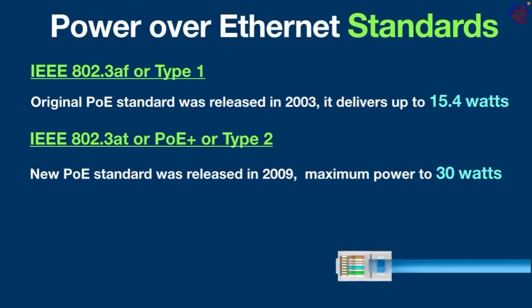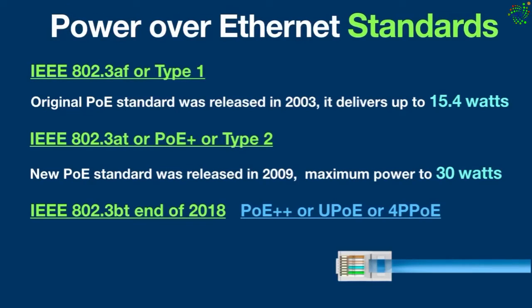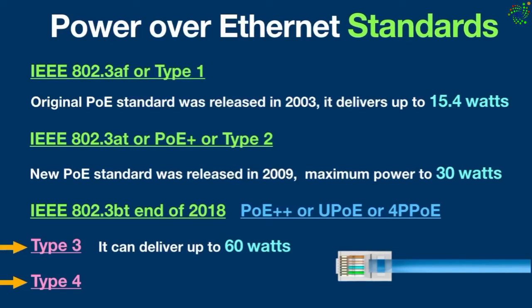30 watts was not good enough for technology like flat screen displays, LED lighting, or POS terminals. To meet the demand for high power, a new PoE standard, IEEE 802.3bt, was released at the end of 2018. It has different names such as PoE++, Ultra PoE, and four-pair PoE. This standard is further broken down into two types: Type 3 can deliver up to 60 watts over four pairs of wires, and Type 4 can deliver up to 100 watts from the PoE switch to power devices, enabling applications such as LED lighting, security card readers, intercoms, and laptops.